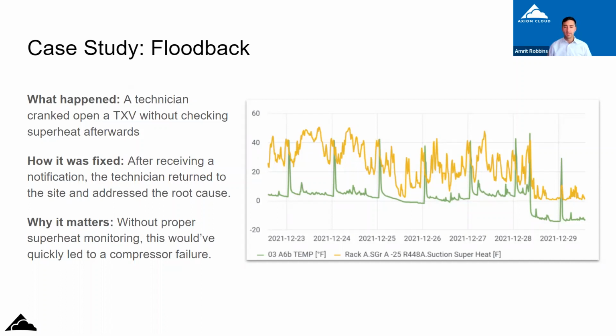And so you can see that basically a technician came in and cranked open a TXV, and that caused the temperature to get down to where it needed to be. So that was the make-the-food-cold type move. However, that also caused the suction superheat to drop to 0 on that particular suction group. And so this is an example of making the food cold, but not solving the root cause of the problem. By using data to look at these trends, we could identify, hey, these two things happened at the same time. The temperature got fixed, but the superheat dropped to zero at the same time. This is not rocket science, but by looking at that historical data and making that comparison, that was enough to help us figure out the root cause of that suction pressure, the suction superheat issue.